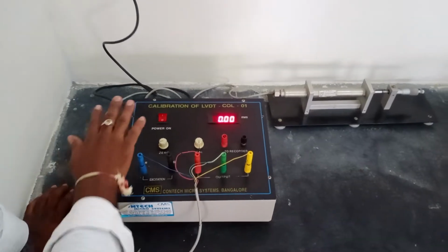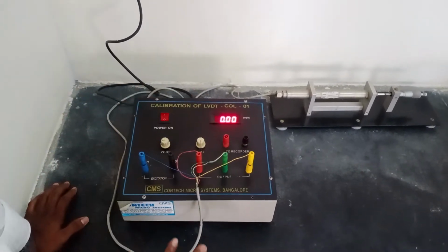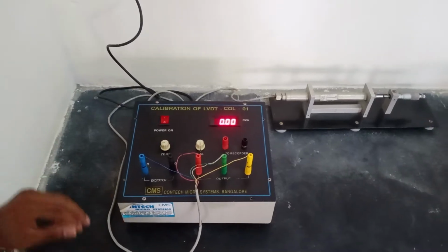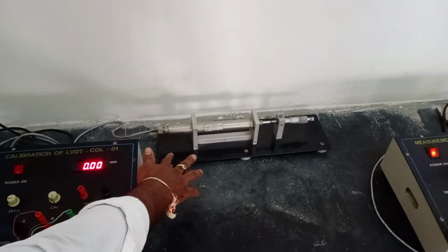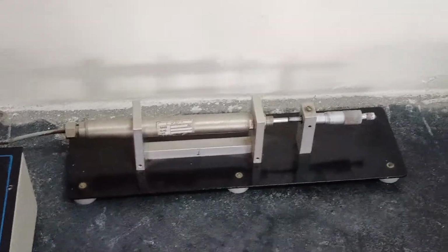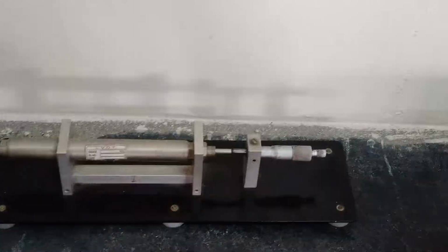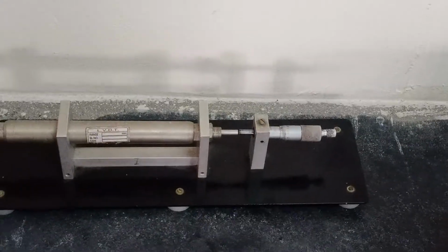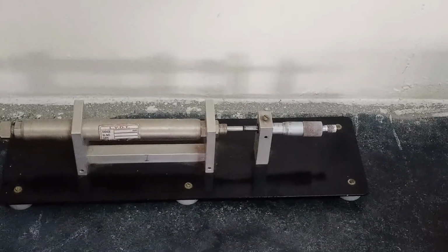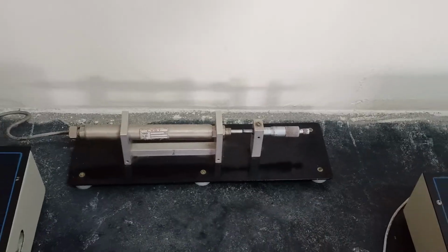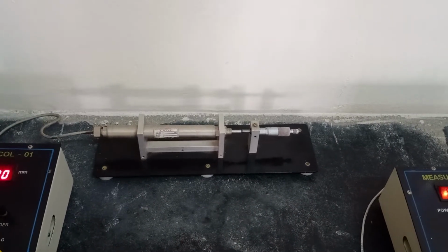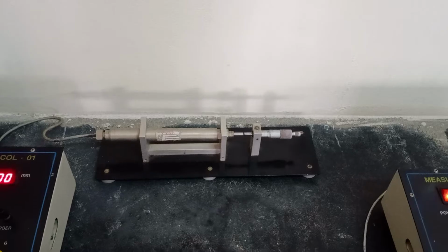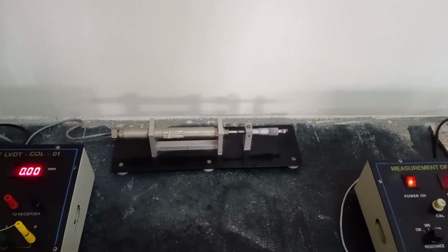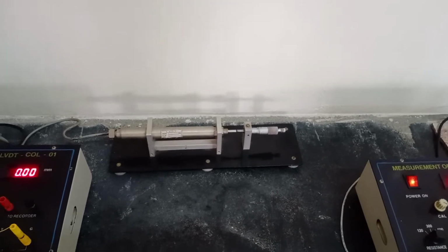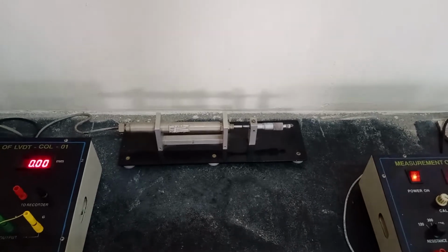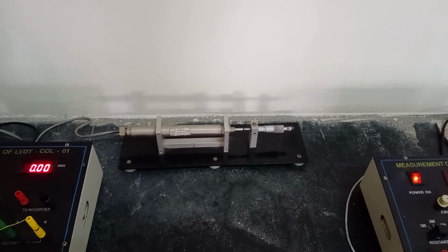On the device, power is already on. This is the LVDT display. The core is connected here, and the micrometer is connected here. One complete rotation of the micrometer is half a mm. Two rotations complete 1 mm, because on the micrometer scale there are only 50 divisions, hence two rotations are needed for 1 mm.